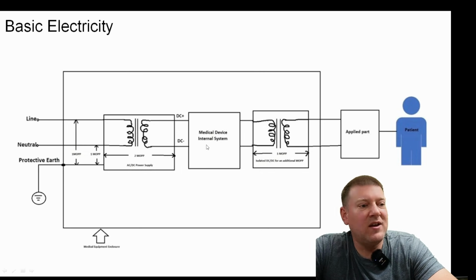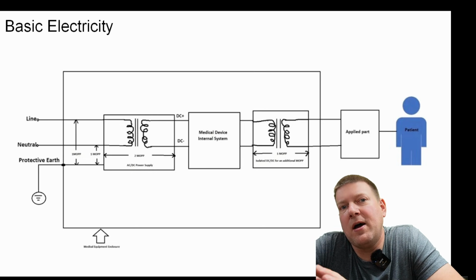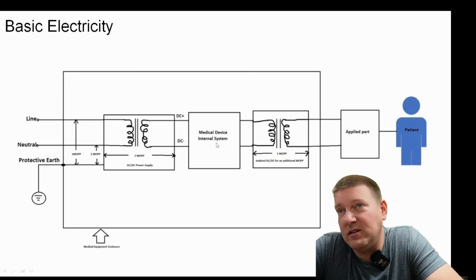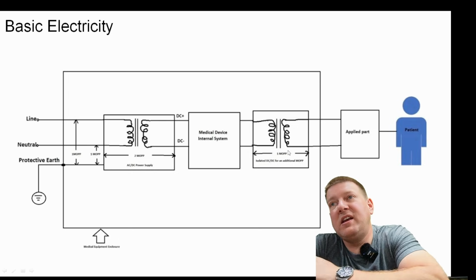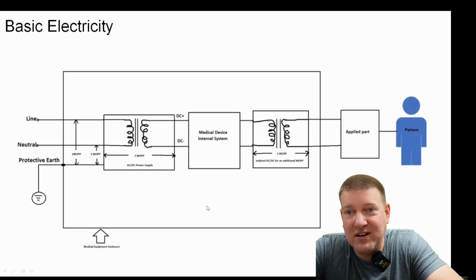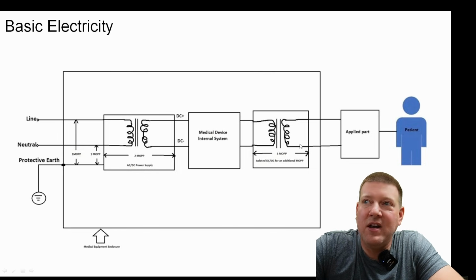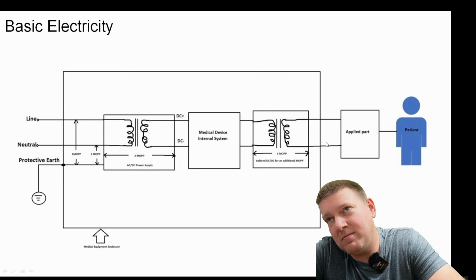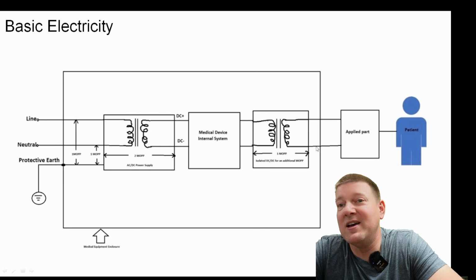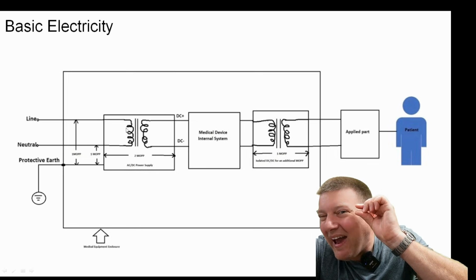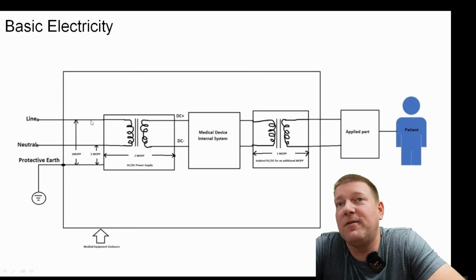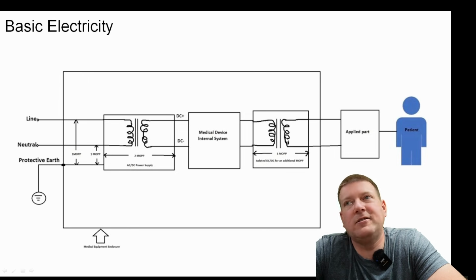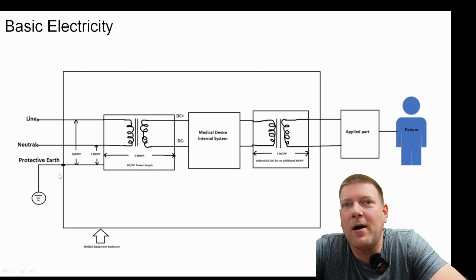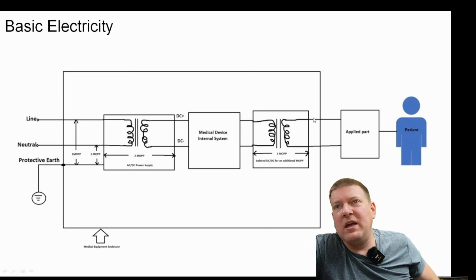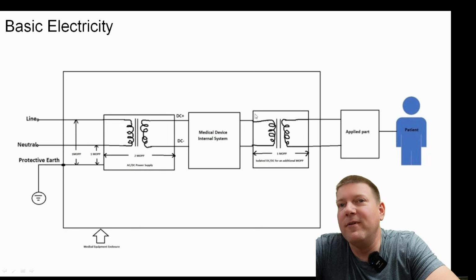What's interesting is there are systems inside a medical device, like a computer, that can create leakage and create noise. So by isolating it yet again, you are isolating leakage and noise all over again. And down here, you can see that we have the applied part, which touches the patient, and it is 100% safe because there is such a tiny, tiny percent chance of getting any of this leakage from this side over here to this side over here. It's really hard, okay? If the enclosure is grounded, then this cable right here would have to wear on the case or something like that, okay? So this would be like a double insulated system. It's very safe.